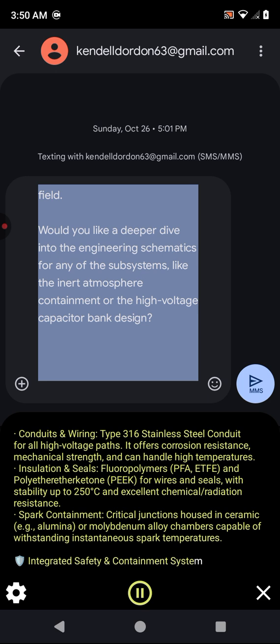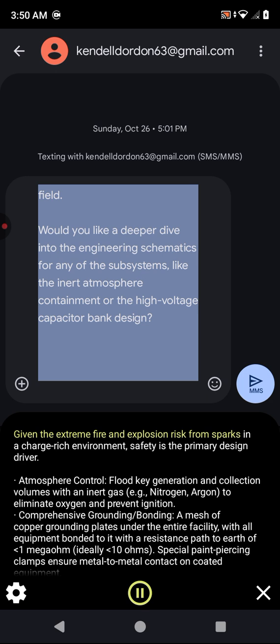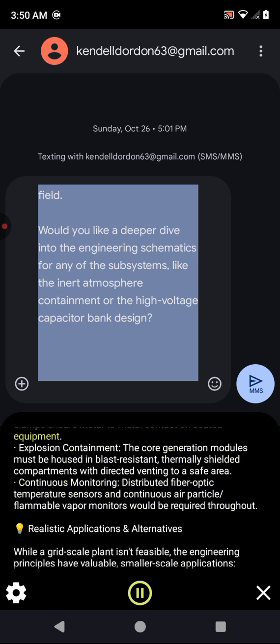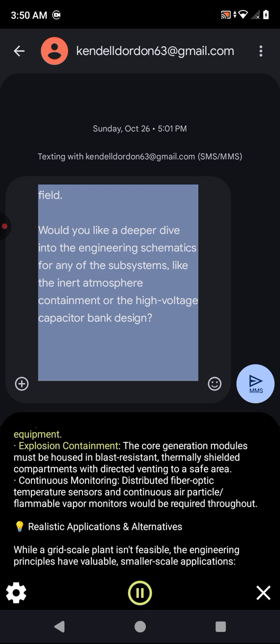Integrated safety and containment system. Given the extreme fire and explosion risk from sparks in a charge-rich environment, safety is the primary design driver. Atmosphere control, flood key generation and collection volumes with an inert gas, e.g., nitrogen, argon, to eliminate oxygen and prevent ignition. Comprehensive grounding and bonding, a mesh of copper grounding plates under the entire facility, with all equipment bonded with a resistance path to earth of less than 1 megohm, ideally less than 10 ohms. Special paint-piercing clamps ensure metal-to-metal contact on coated equipment. Explosion containment, the core generation modules must be housed in blast-resistant, thermally shielded compartments with directed venting to a safe area. Continuous monitoring, distributed fiber optic temperature sensors and continuous air particle and flammable vapor monitors would be required throughout.